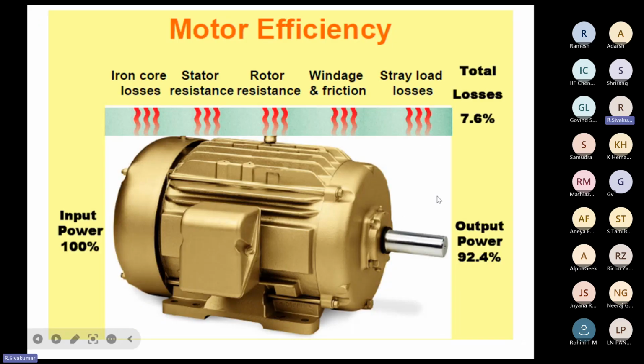The second thing is, out of this melting area, motors are used in all the industries. Motor efficiency is classified by the input power and the output power. Normally the old motors have the EFF1 standard, and many foundries are still using the old efficiency motors. Now it comes with IE, which means international efficiency: IE1, IE2, IE3, IE4. IE1 is no longer in the market; IE2, IE3, IE4 are. Now IE5 is also in the market.